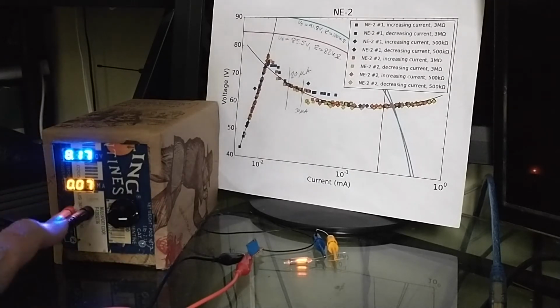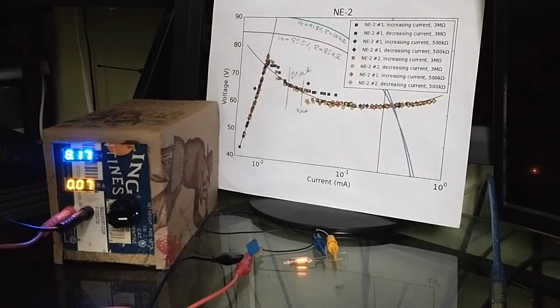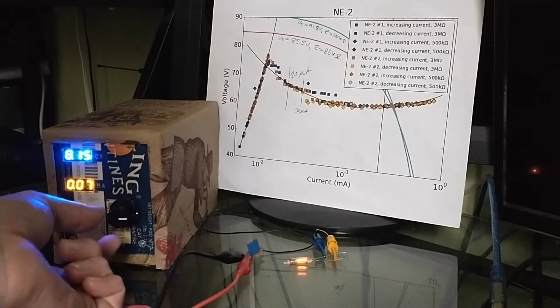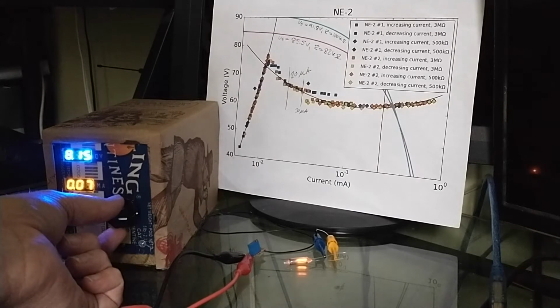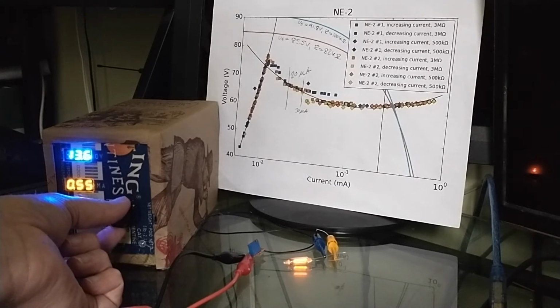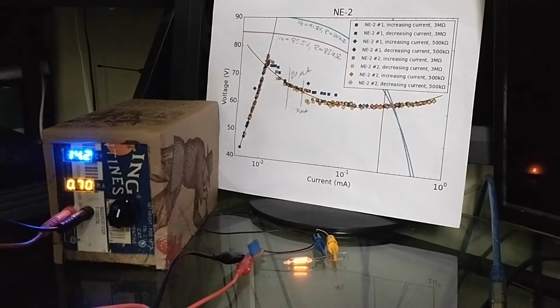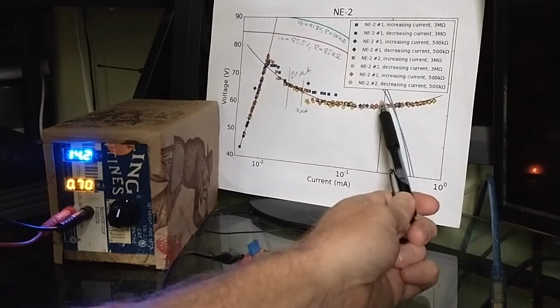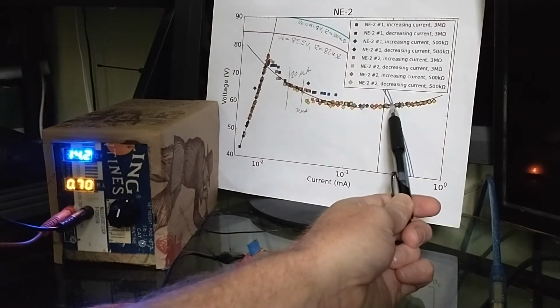Here the current is pretty low, it's only 70 microamps. So you probably want to get a little bit higher to be in a more stable part of the operating regime. So we're going to crank this up, half. And that's about as high as we can go here. So now we're operating this at 0.7 milliamps, which puts us right around here on the curve, which is a pretty good operating point.